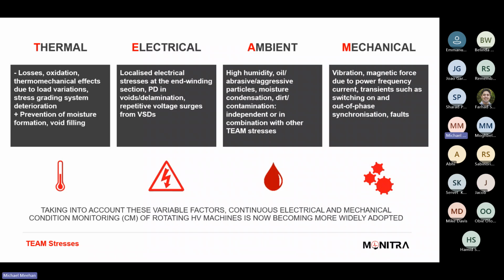So we looked at ambient. We look at ambient, we think of moisture in the oil, obviously, plus dirt, local electrical stresses. You're going to end up with some issues if you don't maintain your bearings and that lubrication system in the right way. Some of the bearings, white metal, and the speeds and the heat that can be generated and everything else, the bearings themselves are probably the most critical feature of the machine, but there's well-established techniques to manage, maintain and monitor the condition of the bearings and the oil systems that are associated with those.